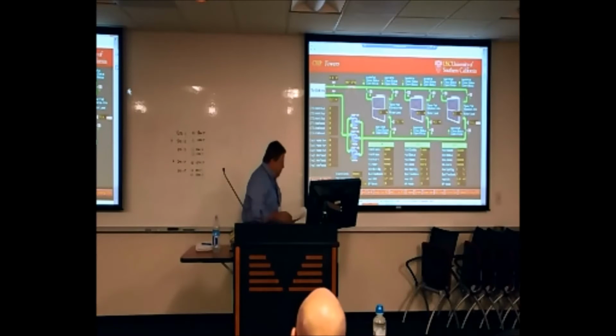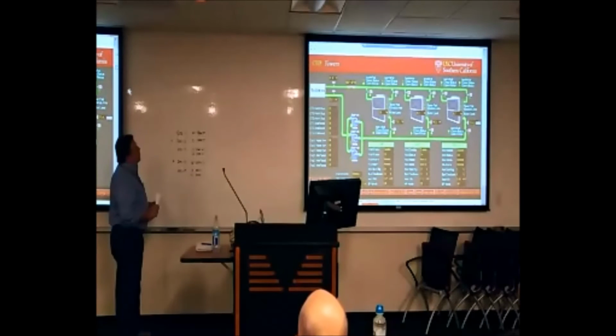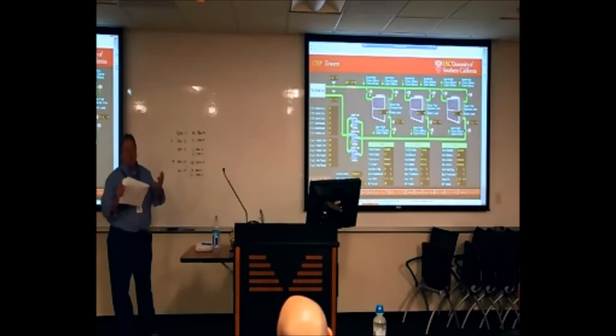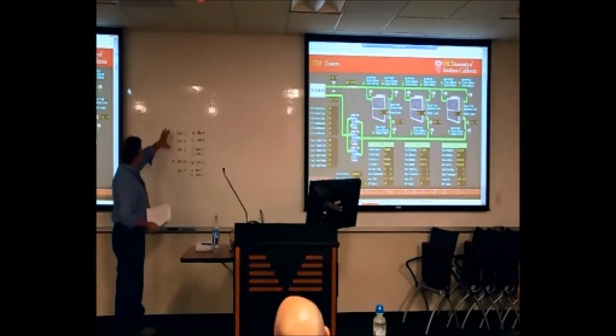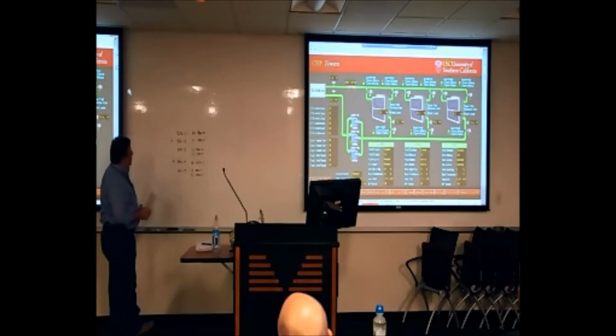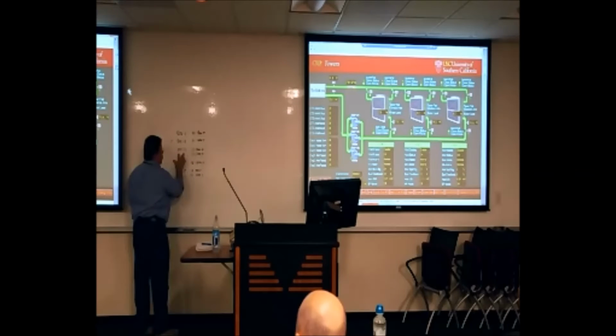One other, I guess, let me first talk about the staging over here. We're about to add an 800-ton chiller into the software sequence for the plant. Right now, I think it's 150-ton, Craig, or 100-ton, some little tiny chiller. That became almost ineffective. So now an 800-ton is coming into play. So the software sequence describes how they wanted the staging to go, and I defined a stage 1, stage 2, stage 3, stage 4, and stage 5 based on how they wanted it to operate. Stage 1 is going to be the one new 800-ton chiller, which is not yet online. Stage 2 is going to be the one 1,500-ton chiller, one of the existing chillers. Stage 3 is going to be the one 800-ton, again, that future chiller about to come online, and one 1,500-ton. Stage 4 is 2 1,500-ton chillers, 2 existing chillers. Stage 5 is all up. We have the one 800 and the 2 1,500-ton chillers.